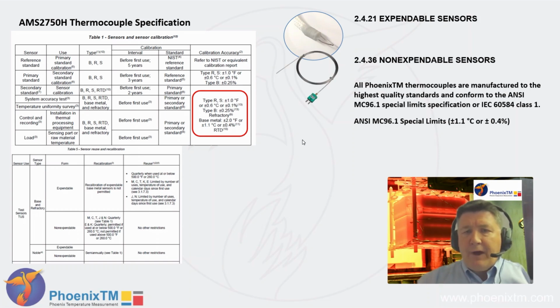Phoenix offer a range of different thermocouples for use in standard temperature uniformity survey work, but it's important to note that all of the thermocouples are rated to either ANSI MC 96.1 with special limits of error, or the IEC 60584 Class 1 specification. For the ANSI spec, all of the thermocouples are rated to plus or minus 1.1 degrees Celsius, or plus or minus 0.4% of the reading being taken, which satisfies the standard that we're working to.